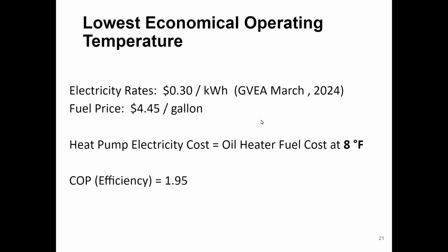Another thing to consider is there's a point at which the efficiency of the heat pump gets low enough that it no longer makes sense to use it against the fuel price you're currently using and the utility rate you have. You can calculate that using that heat pump calculator.